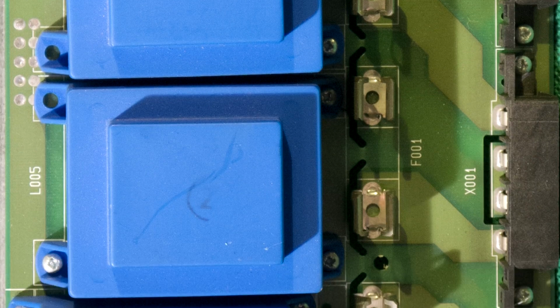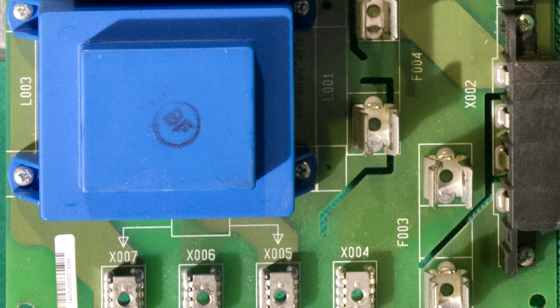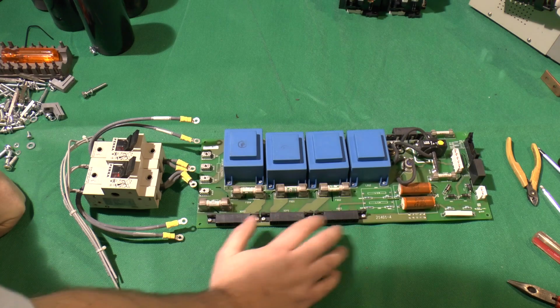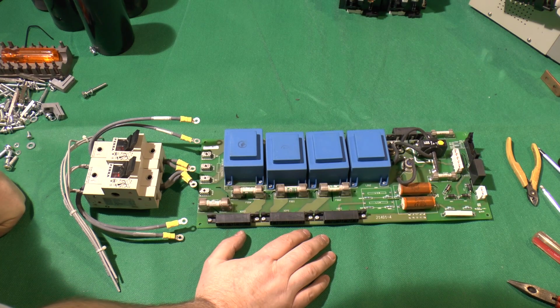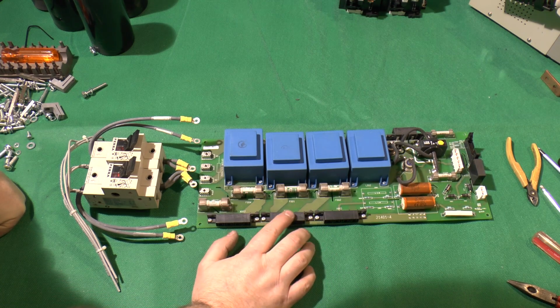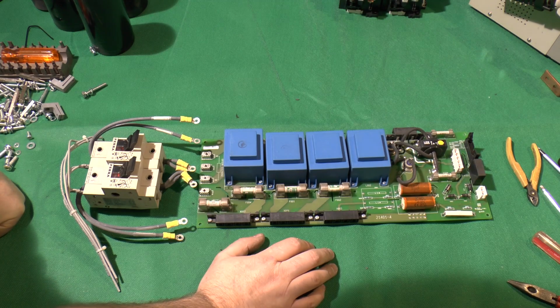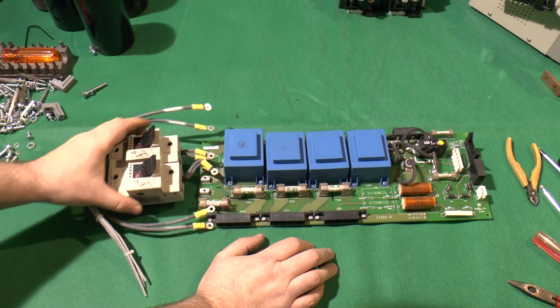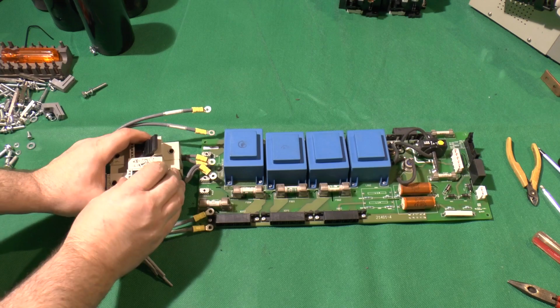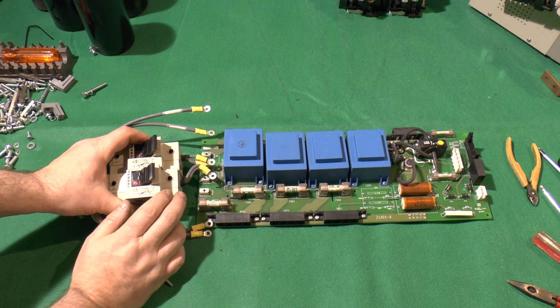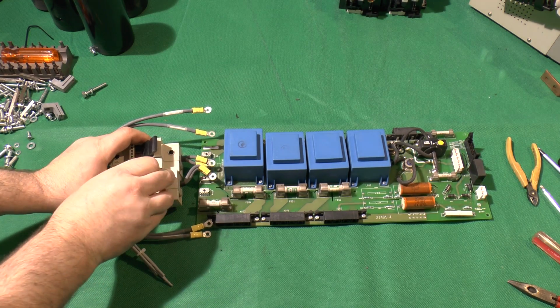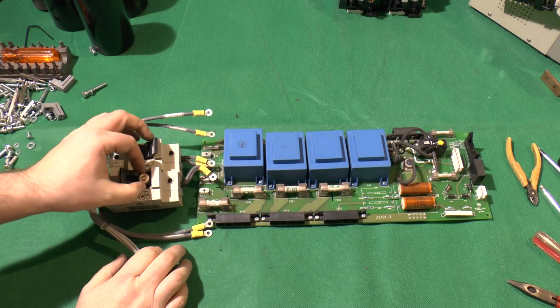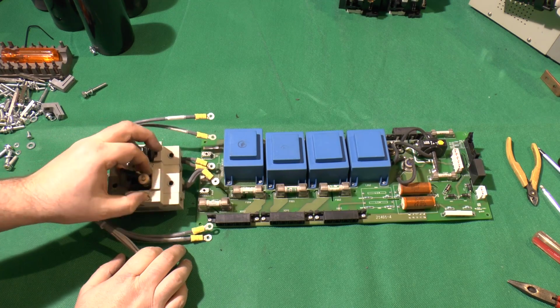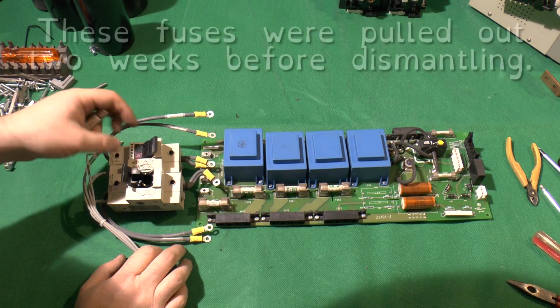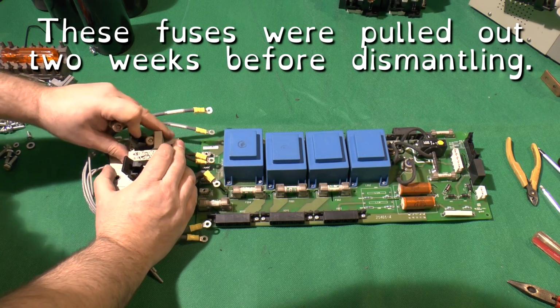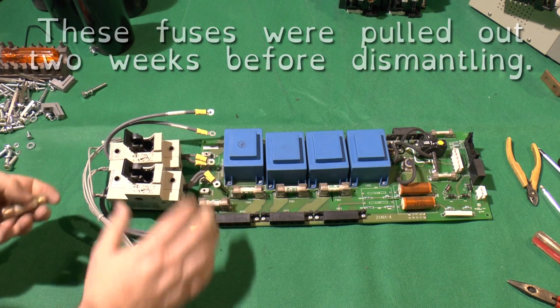There's two 384 volt strings of batteries, basically one long string really, but it connected up here in two halves, and those are actually isolatable. Once you told the system, once you shut the system down, you could actually flip these out and remove these fuses to completely isolate the battery bus.